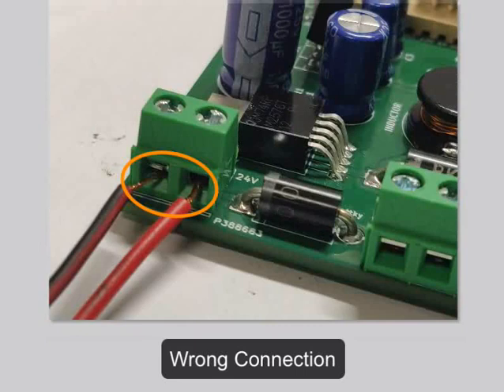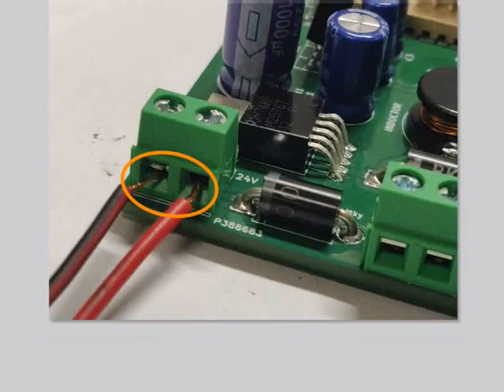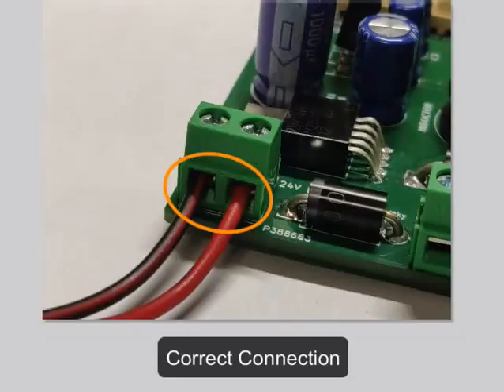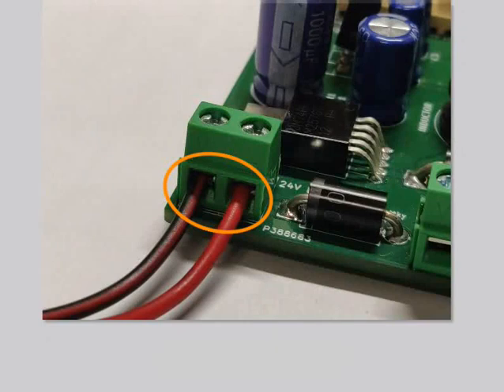While making connections, make sure that exposed metal from the wire is not protruding out. This is a wrong way to connect a wire — we should not connect the wire in this fashion as this may cause electrical shorts later on. This is the right way to connect a wire. Tighten the screws properly and tuck the wire moderately to ensure they are secured in place.